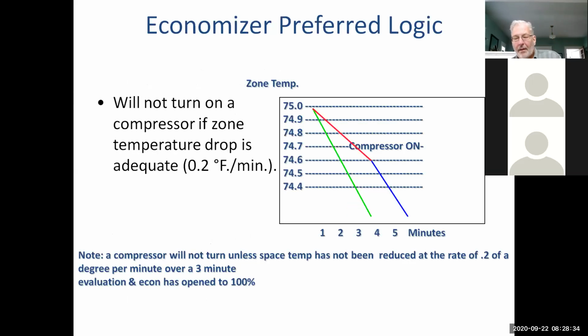So if you're using a Trane thermostat, a DC voltage thermostat, it has the ability to see the space temperature down to 1/10 of a degree. And if you look at the way the economizer works, the compressor will not turn on unless the space temp has not been reduced at a rate of 2/10 of a degree per minute over a 3-minute period, and the economizer has opened to 100%. So in other words, as long as it sees the economizer catching up on the space at that rate, it will not allow compressors to come on, okay?